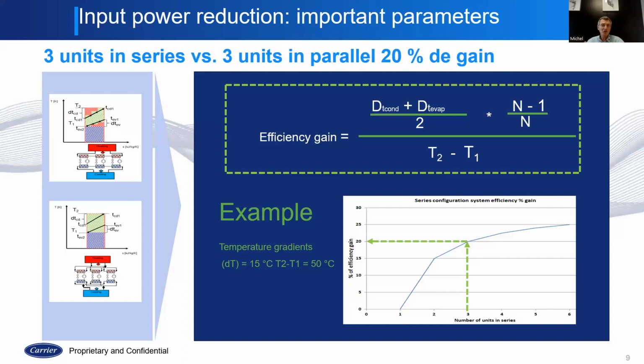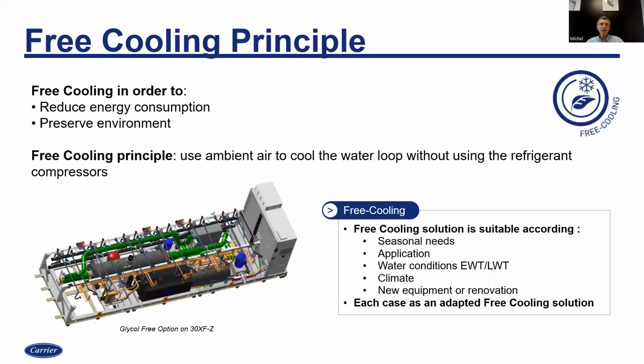But to gain 15, 16%, it's a big challenge without doing a revolution. Frankly speaking, chiller-wise, I don't know how you can improve efficiency of the chiller by 15% when your isentropic efficiency of compressor is about 80, and efficiency and pinch of your heat exchanger is around 0.5. So basically this is the only way to have significant energy savings in the application, by putting machines in series, when it's applicable.